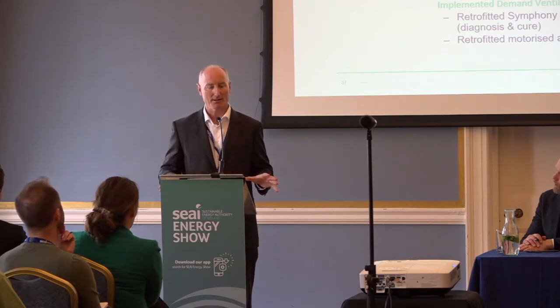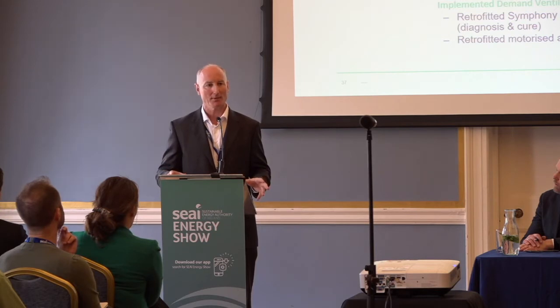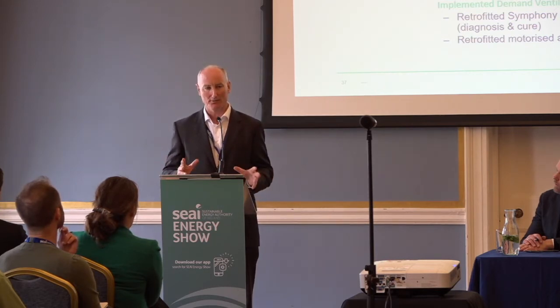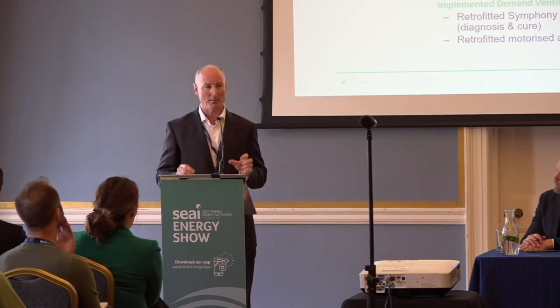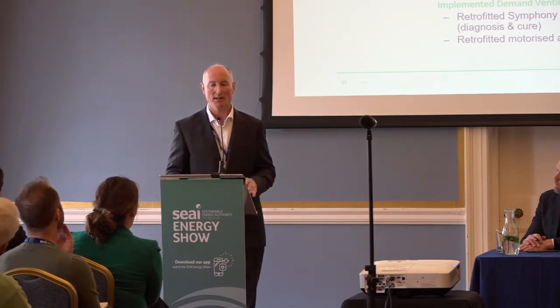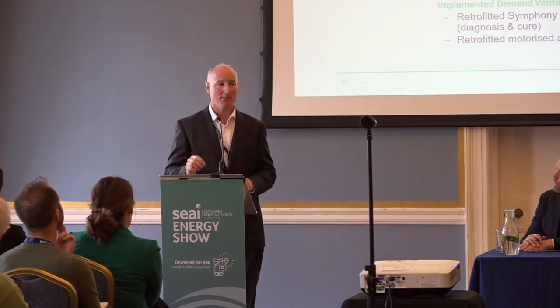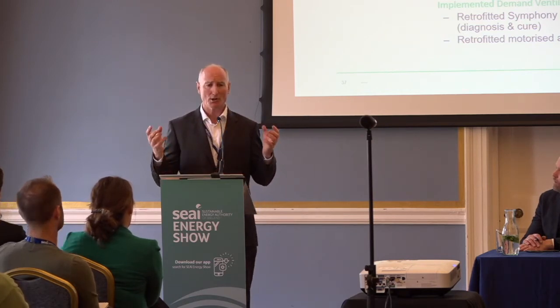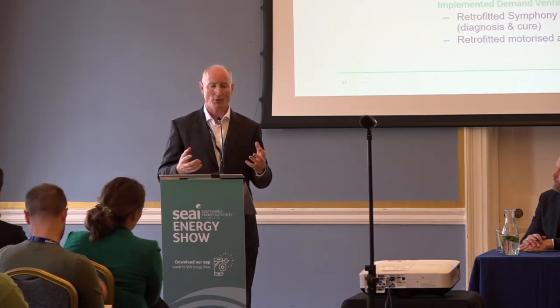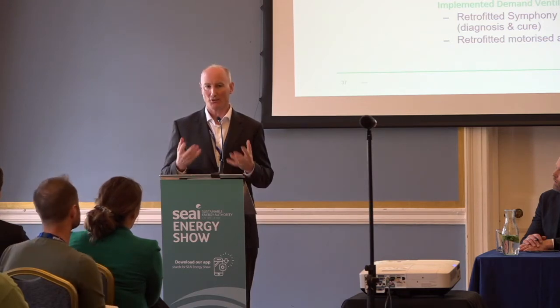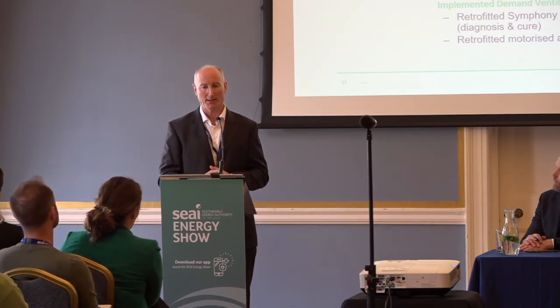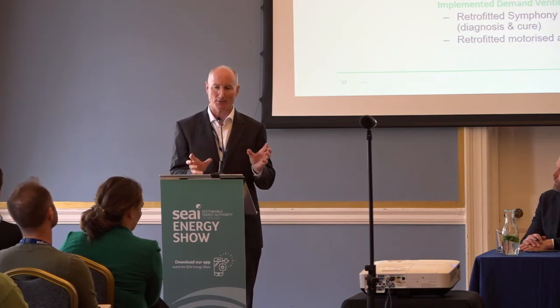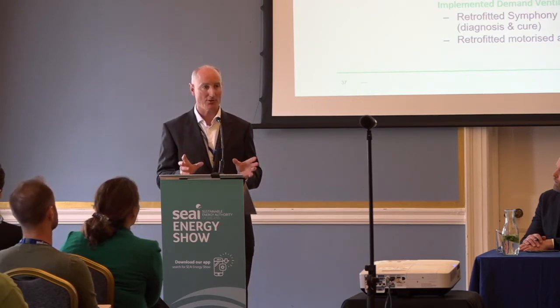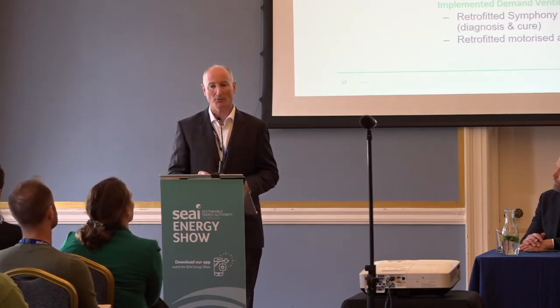In that whole month, the chiller and the primary pump have been entirely off. This is a grade A building with a blue chip incumbent tenant, a household name — they don't tolerate discomfort — yet their cooling chillers and primary pumps have been off entirely so far. That's indicative that with Symphony Cycle you can be getting cooling for probably 6 to 8 months of the year for free. You can't beat that. You cannot beat that. So the tension, the fight between VRF and chilled water, is going to change from this day forward. We're getting free cooling.